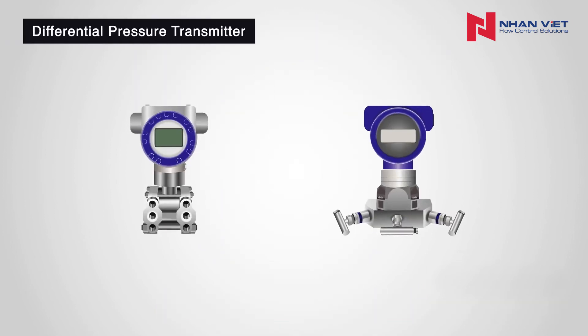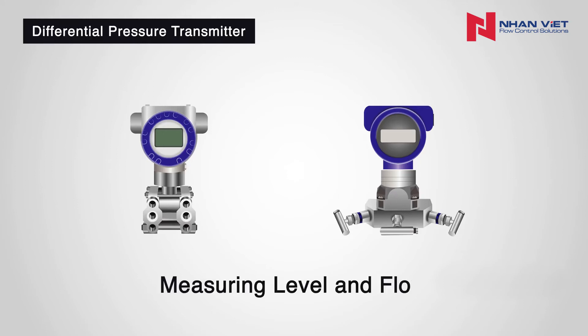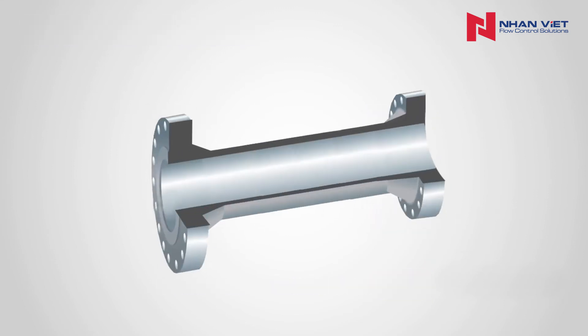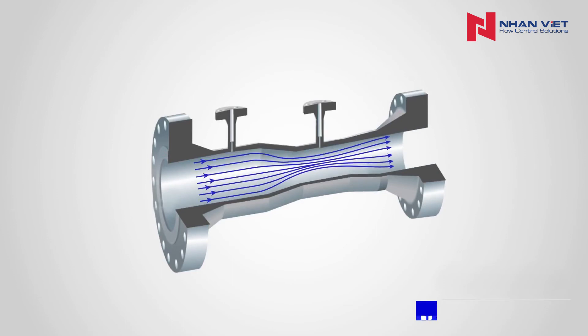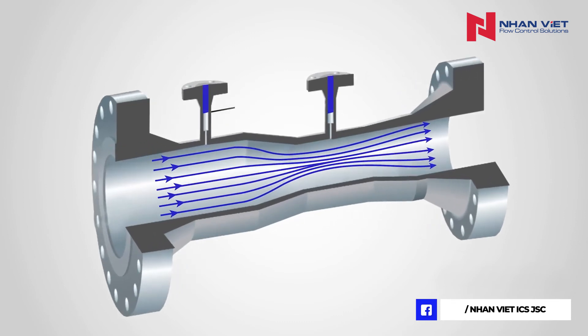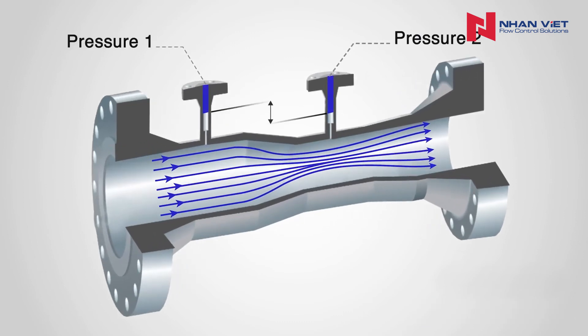Now that we know what pressure is and how a DP transmitter works, what is it used for? The most common applications are for measuring level and flow. Here, we'll discuss how a DP transmitter measures the flow of water in a pipe. One very common way of measuring flow using a DP transmitter is for the primary element to introduce a constriction in the pipe. Using a restrictive element on the primary side will create a high and low pressure. When the flow increases, more pressure drop is created. The secondary element will measure the difference in pressure created by the primary element.